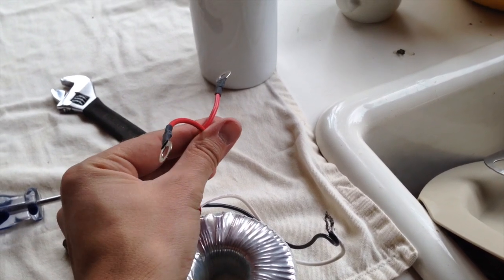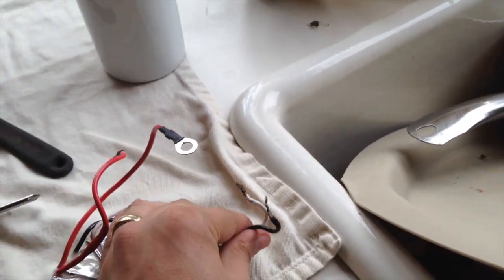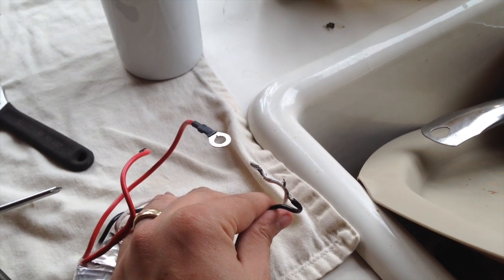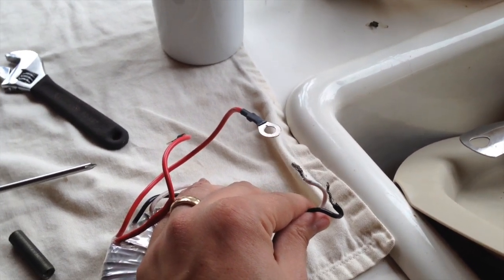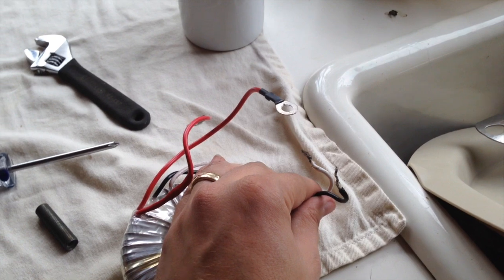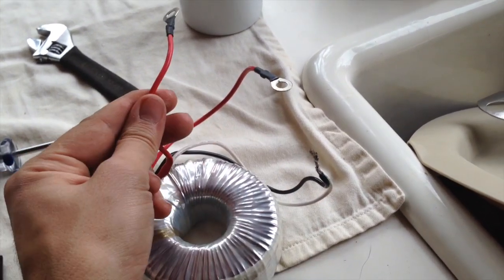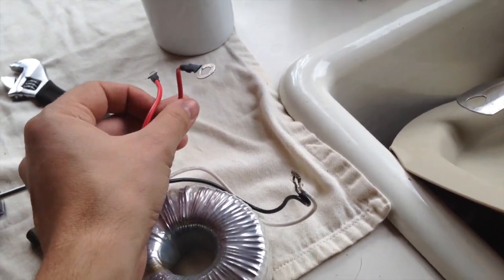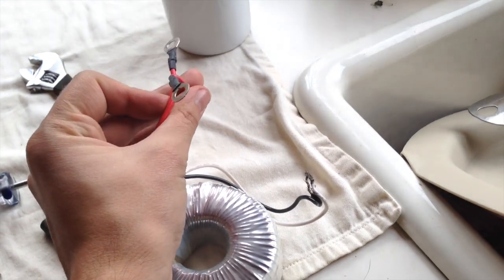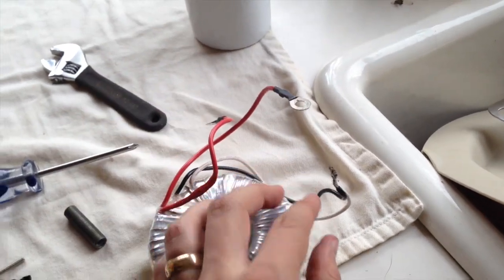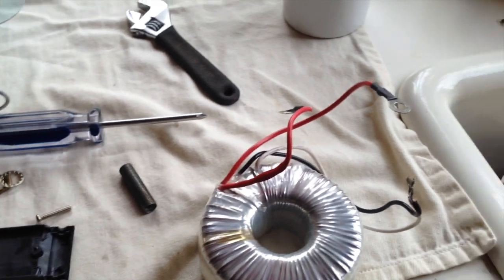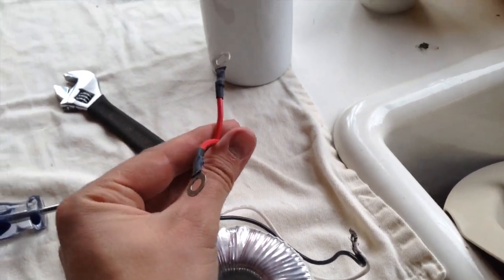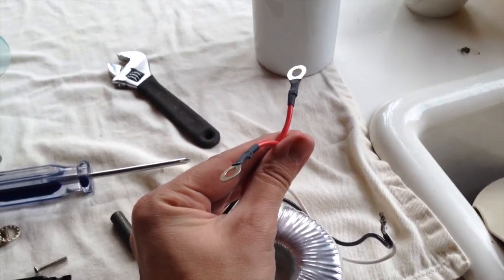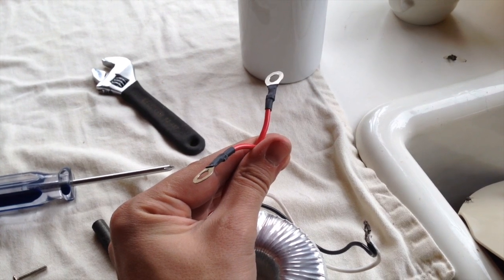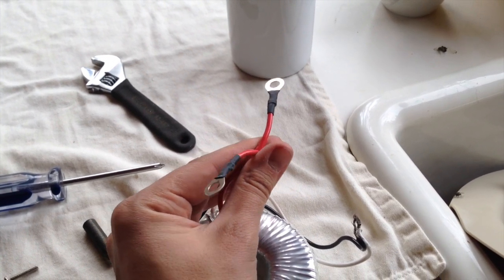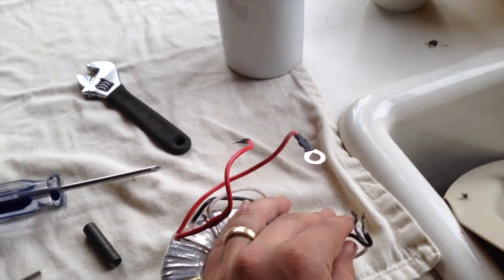These should basically be zero resistance, 0 ohms, or close to it, and so should this. There's just one end of the winding, but they should be open. There should be infinite resistance between the secondary windings and the primary windings. Well, so far everything's checking out. My known good transformer, this is a closed circuit, zero resistance here.